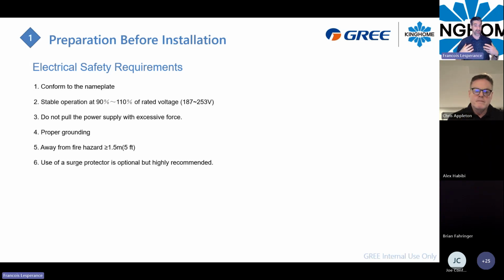You also need a proper grounding. This is really important because you have all those electrical boards inside of it. There is no communication between the indoor and the outdoor unit, but there is some sort of communication inside the unit. So the ground is really important at this point. A proper grounding for the unit is a good thing to focus on.